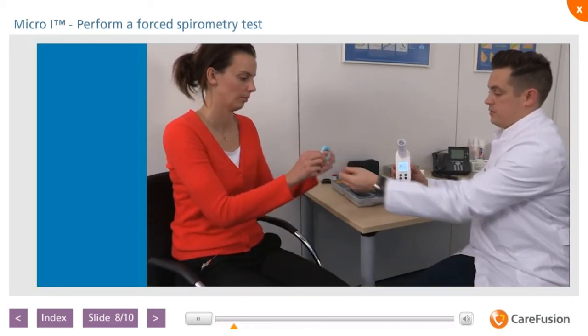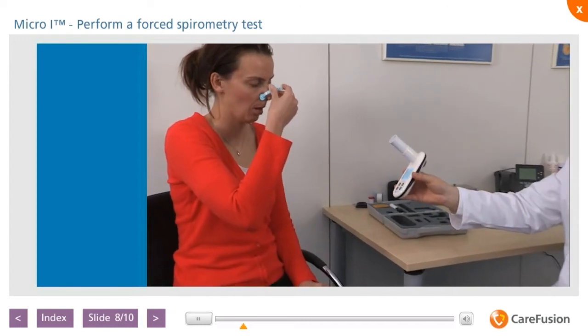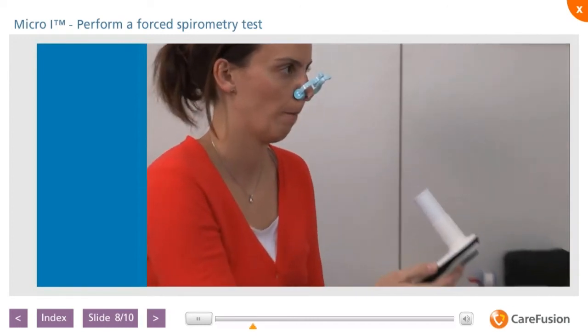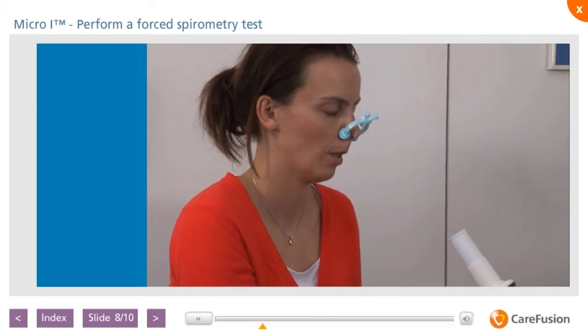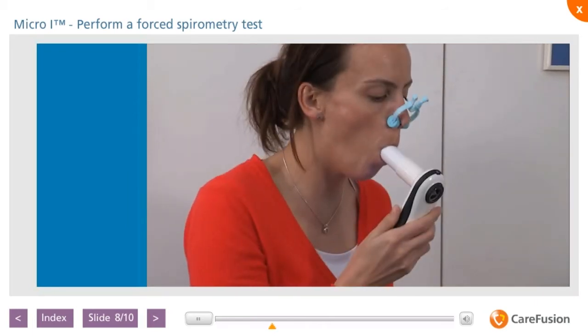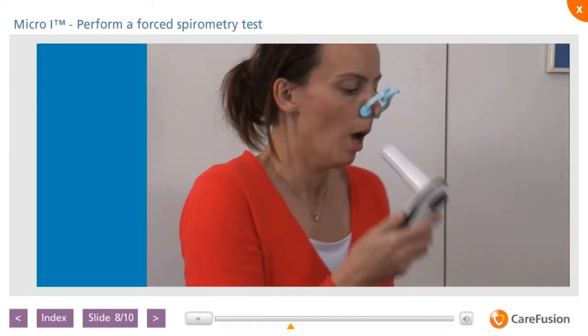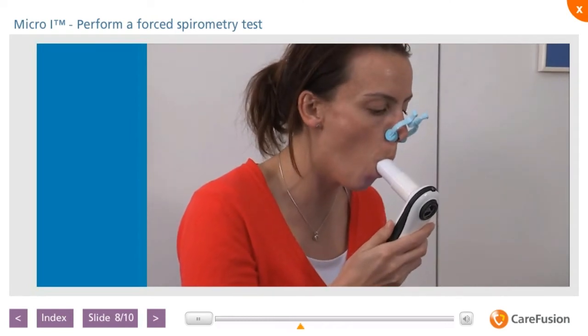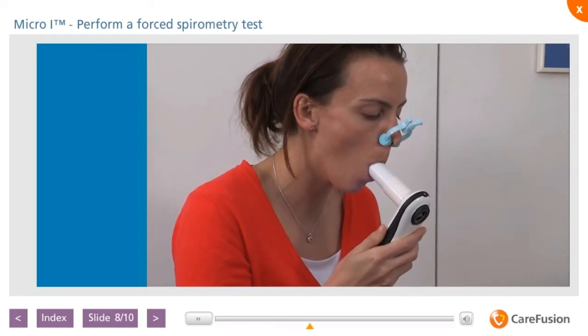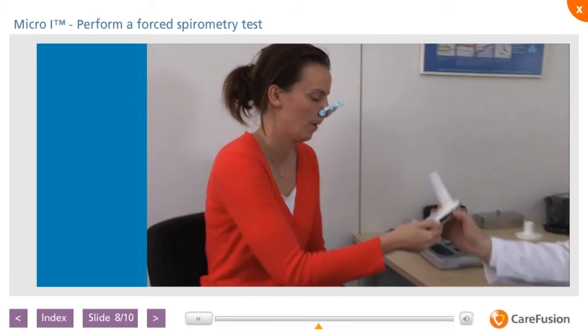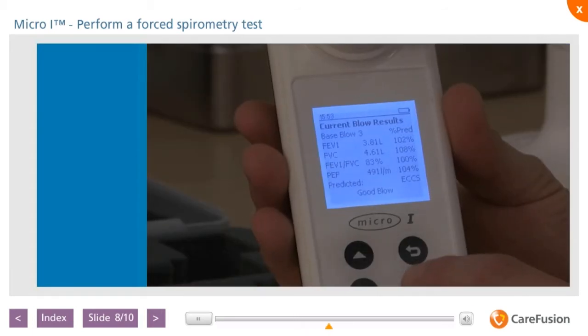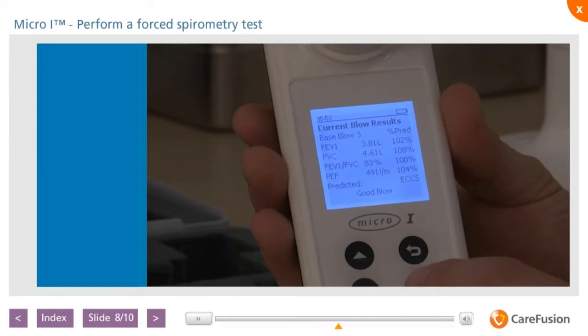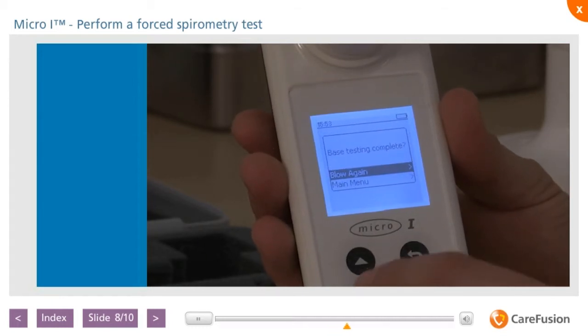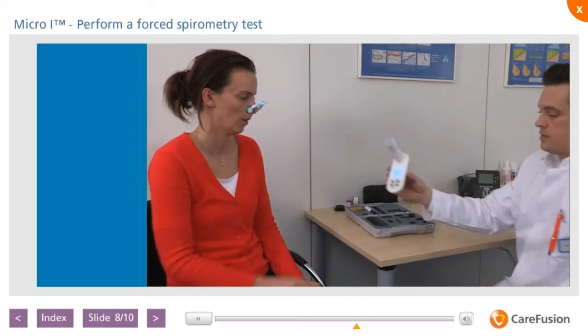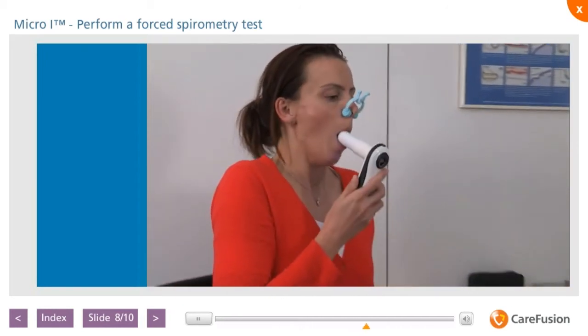Prior to performing a test, ask the patient to place a nose clip on their nose, take a maximum inspiration, and then place the mouthpiece in their mouth, ensuring the patient presses the lips firmly for a tight seal. The patient should then exhale as hard and as fast as possible for as long as possible. Encourage the patient throughout the process to ensure maximum cooperation and effort. To repeat the test, press Enter and choose Blow again. The test should be repeated to obtain 3 good blows.